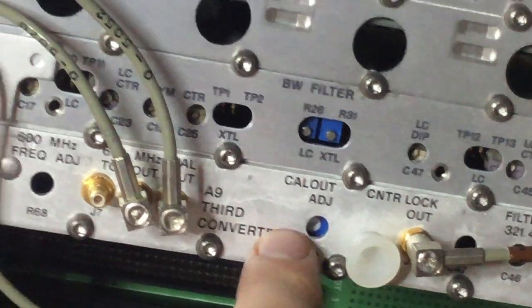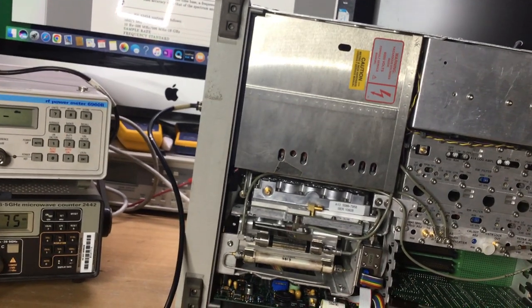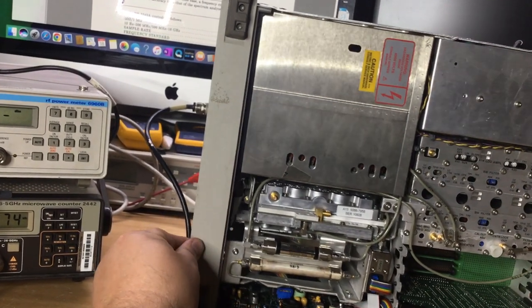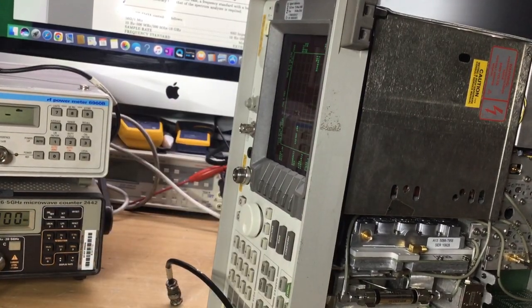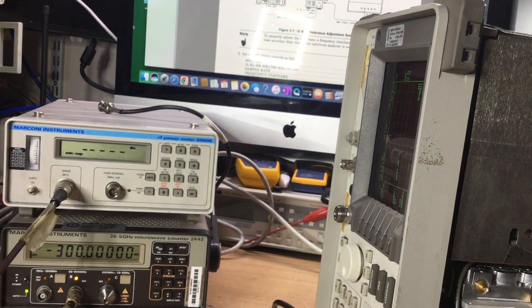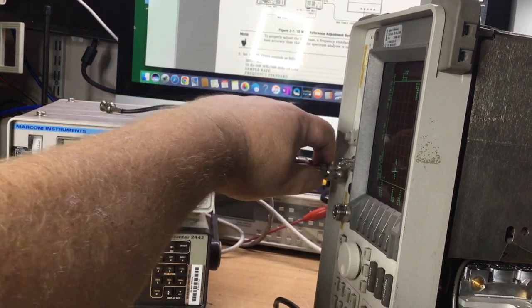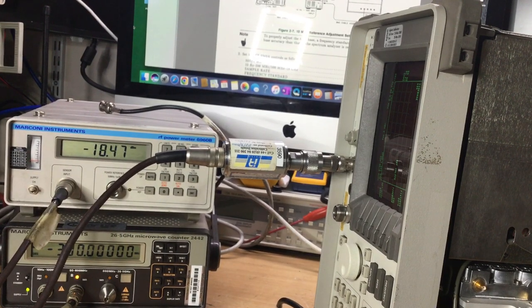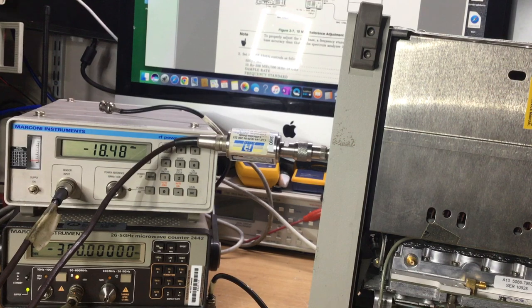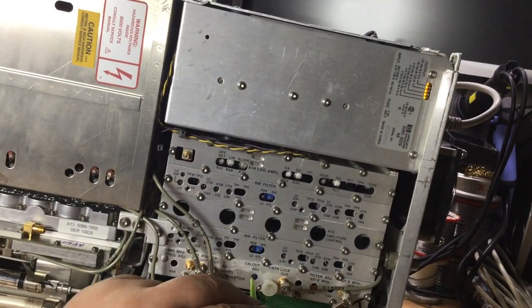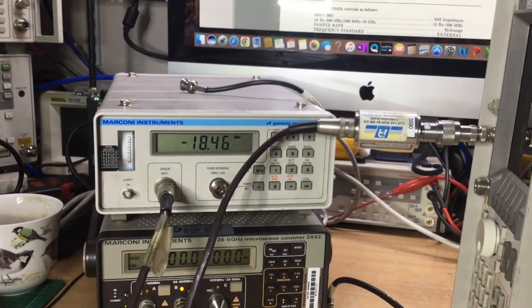So what I'll do, because we've now established that we can't adjust the frequency of the 10 meg oscillator that obviously derives the 300 meg time base for the calibrator, I think we'll just hook up the Marconi level meter now, and we'll make that adjustment on the calibrator output, the RF level output. So we'll do that. So it's reading minus 18 point whatever dBm for the reference level. So what I'm going to do is adjust this calibrator thing. So let's see whether we can adjust that to minus 10 dBm.